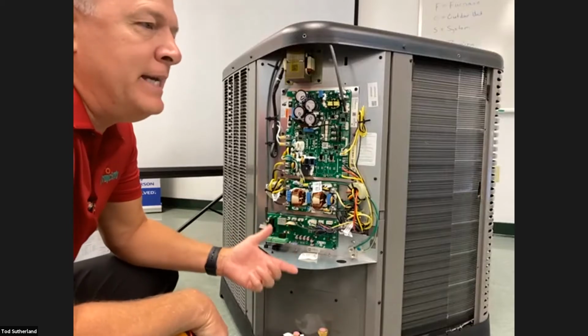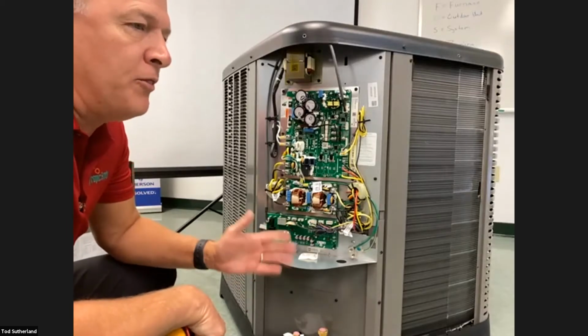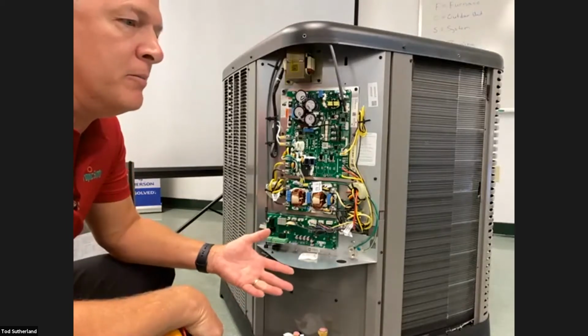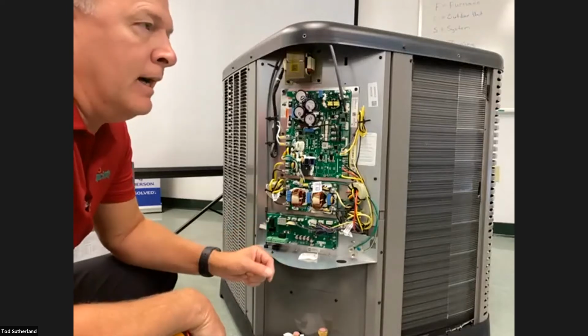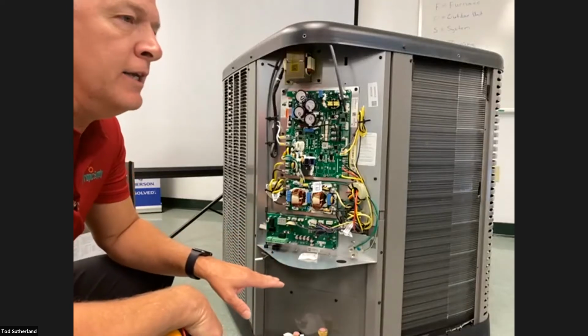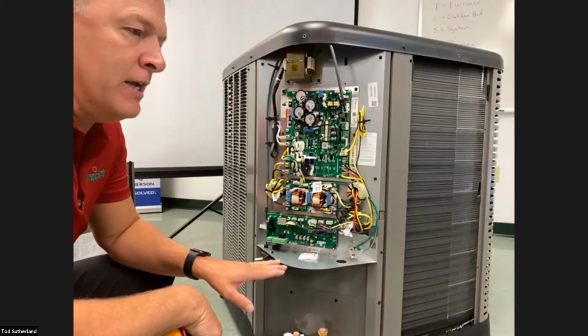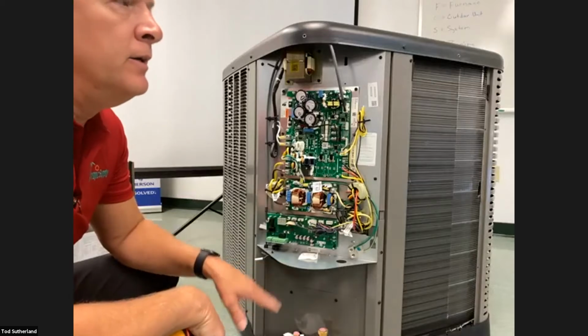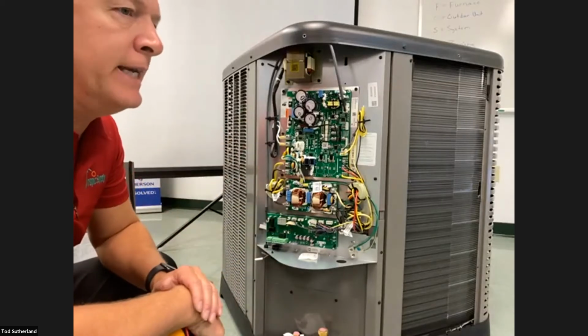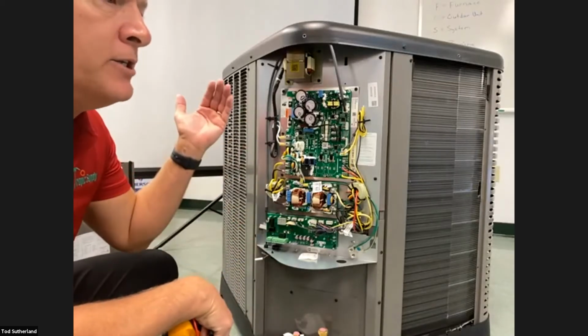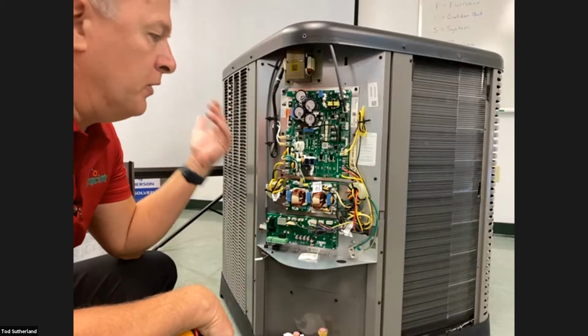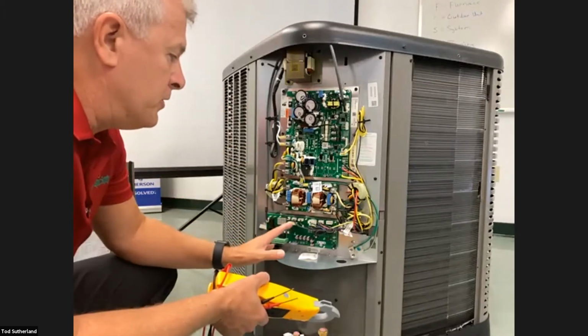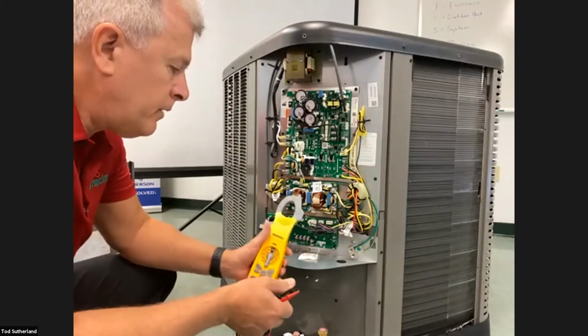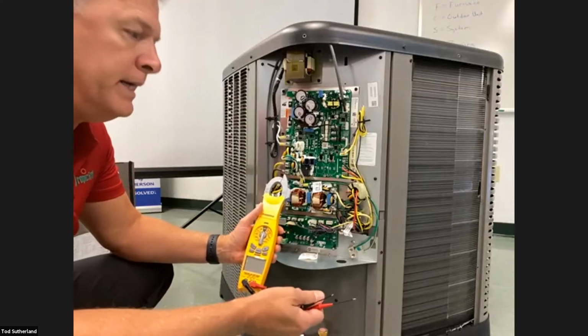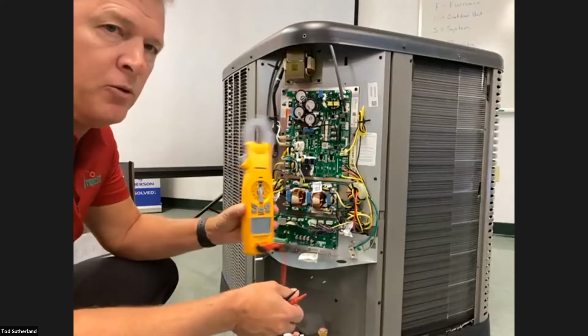Okay. Now what that simply means is the 10K ohm thermistor chart is probably one of the most common thermistor charts there are. 10K ohms is going to equal 77 degrees. From there, your ohms reduce as your temperature gets higher, and the ohms increase as your temperature gets lower. So to verify whether or not your thermistors are operating properly, you're simply going to take your ohm meter.